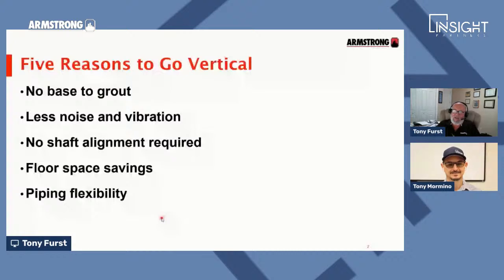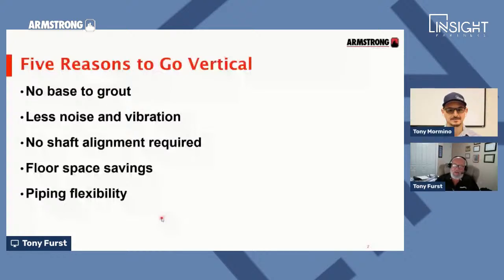Yes, seismic is an issue with any piece of mechanical equipment. The biggest issue with vertical inline pumps is the overturning moment. The pump's not going to turn over in a seismic event because it's bolted to the piping and the piping is rigid - it won't actually fall over. But understand there are overturning moment forces applied to that pump and to the pipe flanges.